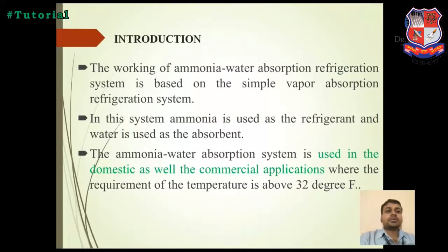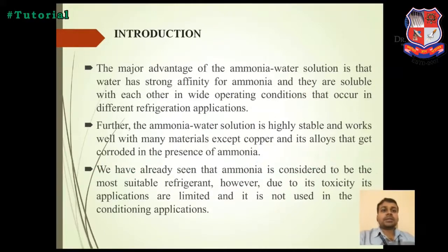The ammonia water absorption refrigeration system is used in domestic as well as commercial applications where the required temperature is above 32 degrees. For running this system smoothly, an atmospheric temperature of 32 degrees is required, and nowadays it is commonly used for domestic as well as commercial applications.